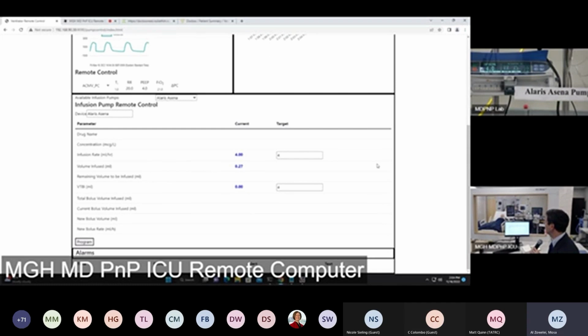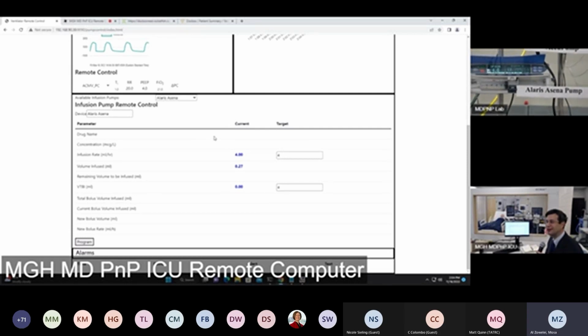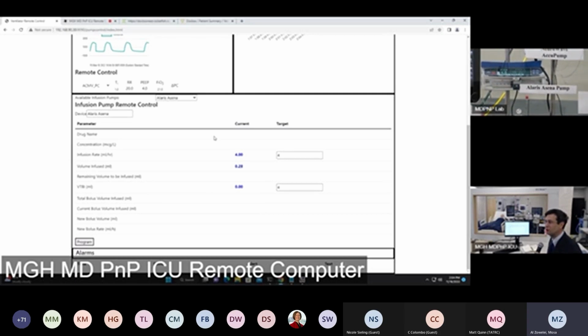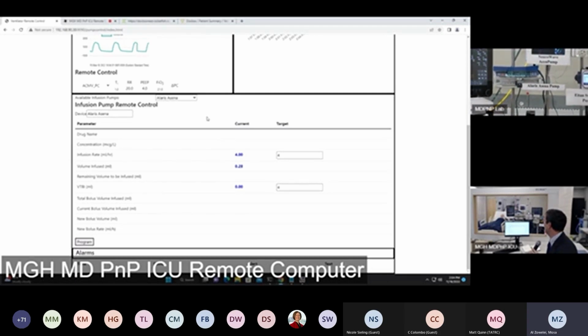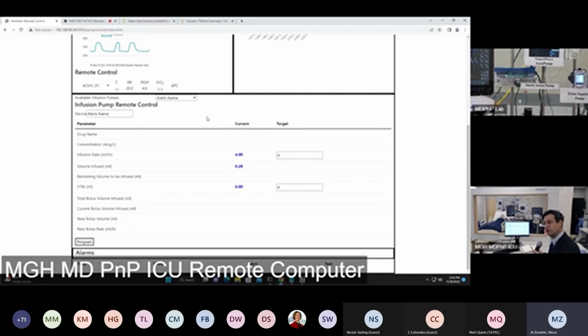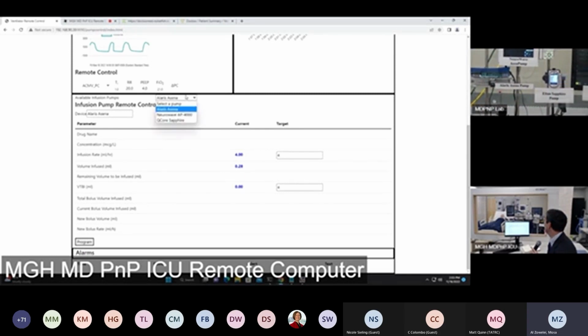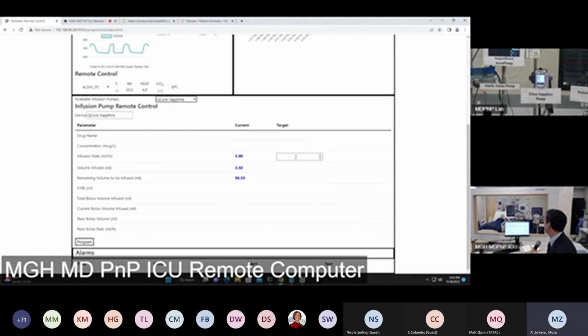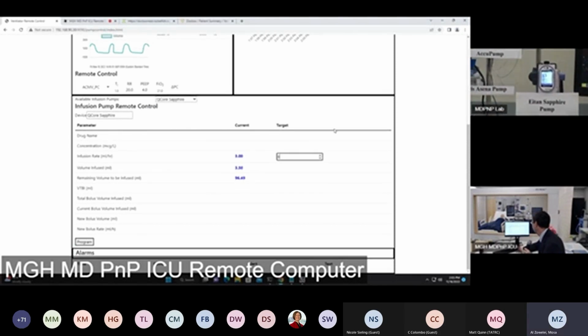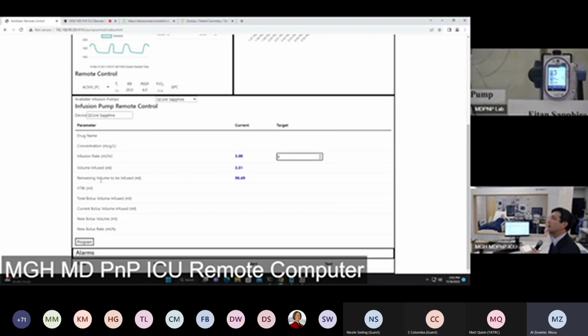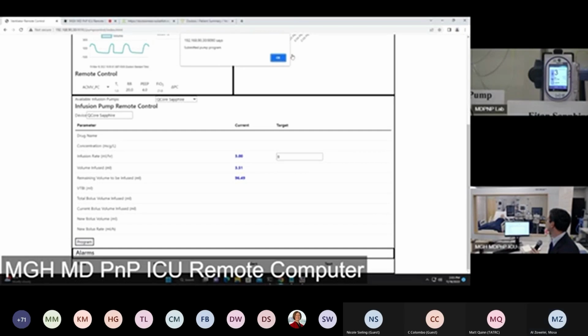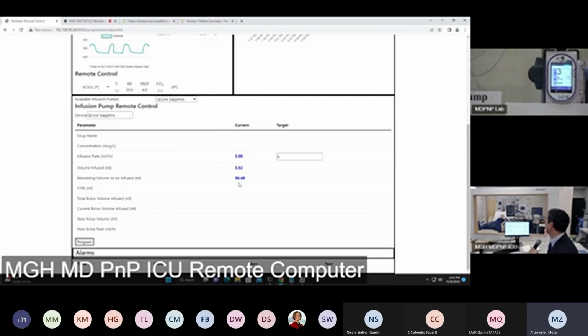And it's the same user interface here. We can see we don't get all of the data elements that we get from the NeuroWave. We don't even see the drug name. And for safely controlling infusions remotely, knowing what drug it is is pretty important. That's one of the things that you would really need to see. But we are able to work with this pump, even though it wasn't built for these kinds of use cases, using that interface that's available. Similarly, with the Q-Core Sapphire, we can change the rate remotely. So I can change that from a rate of 3 to a rate of 8. Just click program. It'll push through. Again, we've got only one thing where we can actually make a change to the pump. We can only change the rate, and it's not populating most of the boxes.